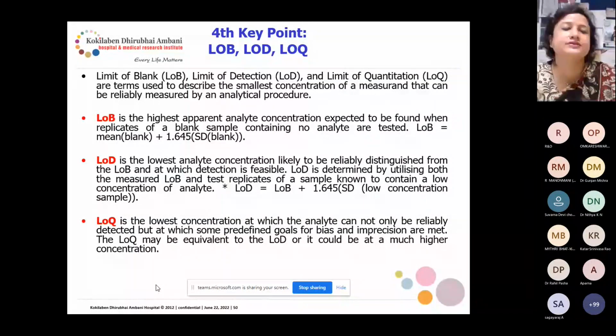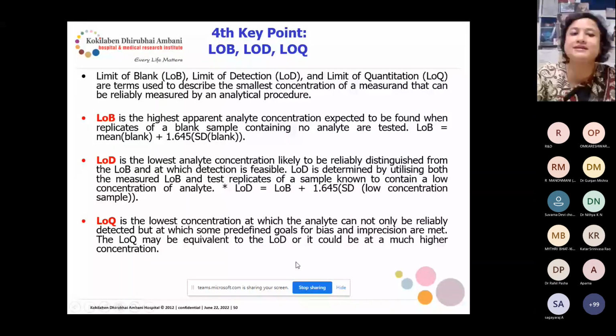These are the terms used to describe the smallest concentrations of a measurand that can be reliably measured by any analytical procedure. Limit of blank is the highest apparent analyte concentration expected to be found when replicates of the blank samples containing no analytes are tested. So this is the formula for limit of blank. And then limit of detection is the lowest analyte concentration likely to be reliably distinguished from the limit of blank and at which detection is feasible.